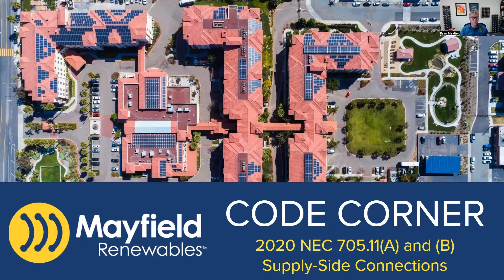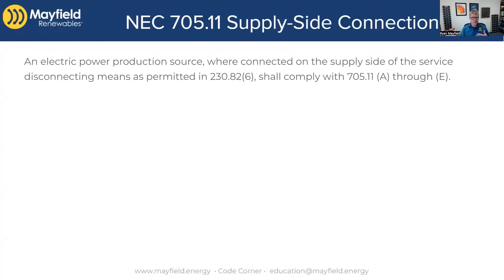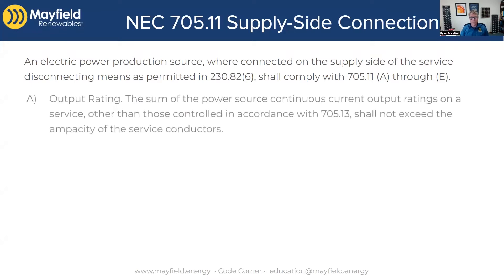Code has now given us some very good rules on how to make these connections where we didn't have them before. So let's jump in and talk about a couple of these. 705.11a is what we're going to focus on first. What it's saying is that an electric power production source, such as a PV system — that's a generic term but it applies to our PV systems — if it's connected on the supply side of the service means, then we have to go through 705.11a through e. And so 'a' is where we're focused.